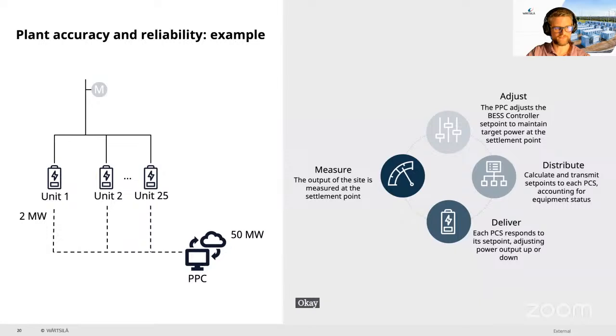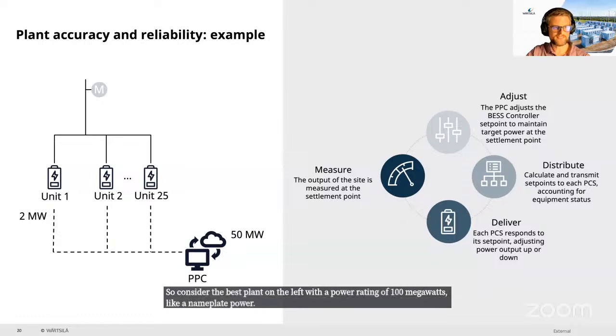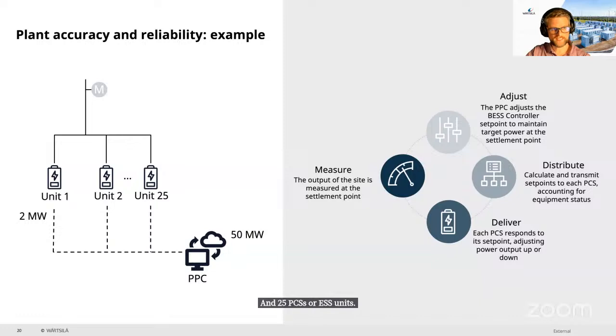To highlight the benefits of using a closed loop controller, we'll walk through a short real world example. Consider the BESS plant on the left with a nameplate power rating of 100 megawatts and 25 PCSs or ESS units. The plant is following a 50 megawatt dispatch signal from the central dispatch, so that's about 2 megawatts for each unit. One of the PCSs trips offline due to a ground fault or some other fault. As this PCS trips, the power at the point of interconnection, that meter at the top, would drop by roughly 2 megawatts, whatever power that unit was providing.